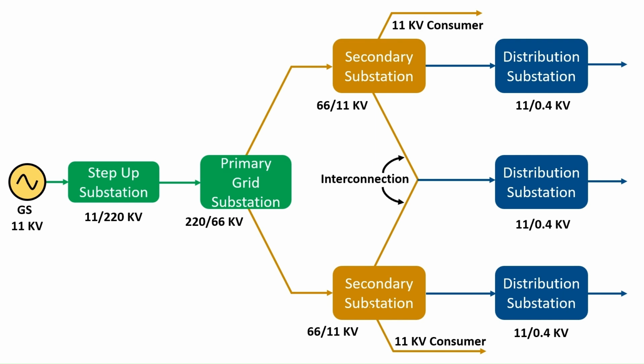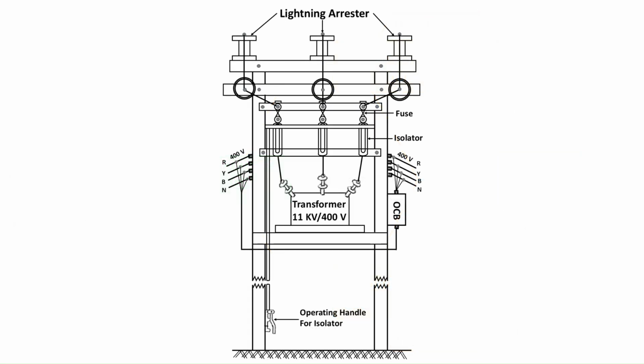The single phase residential lighting load is connected between any one phase and neutral, whereas a 3-phase 400 volt motor is connected across the 3-phase lines directly. It may be noted that the majority of distribution substations are pole mounted. A pole mounted substation is a distribution substation which is placed overhead on poles. It is the cheapest form of substation as it does not involve any building work.